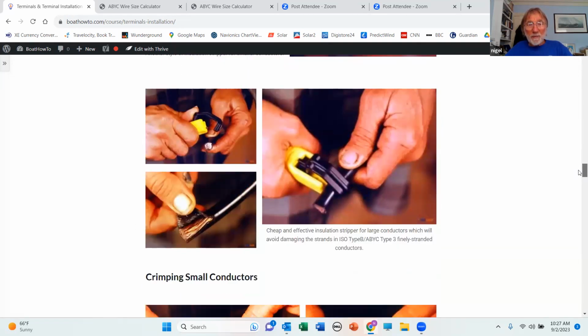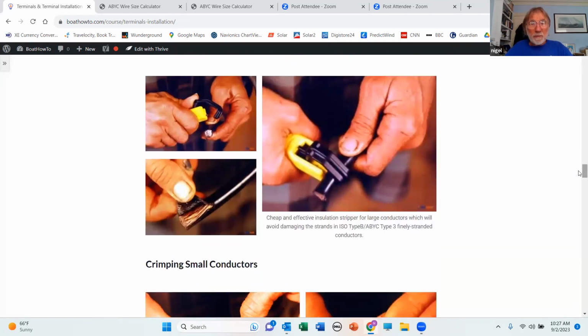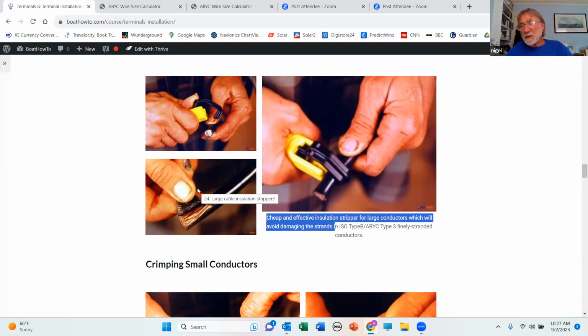When we get to big conductors, all too often people use a pocket knife. But with these stranded conductors, it's very easy to cut through some of the strands. So you want a stripper like this. It's got a little spring-loaded blade in here. You push the housing out around the conductor and then let go of it, and the spring pulls it back against it. And then you run this thing around in a circle like this, and then you pull it sideways, and you'll be able to just peel the insulation off. So we need the right stripping tools.